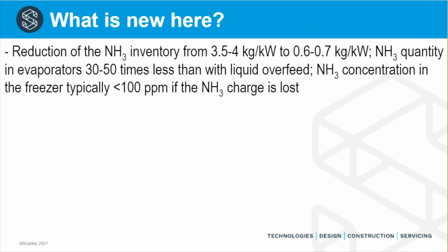So what I've shown you so far, and what is new here, is a reduction in ammonia inventory by about 4 or 5 times compared with liquid overfeed systems. What I haven't explained to you is the very much lower inventory in the evaporators. We are looking at somewhere between 30 and 50 times lower than conventional liquid overfeed evaporators for freeze applications. Because the density of the ammonia is higher at medium temperature, the reduction in inventory for chiller evaporators is not quite that dramatic, somewhere around 20 times lower than conventional liquid overfeed evaporators.